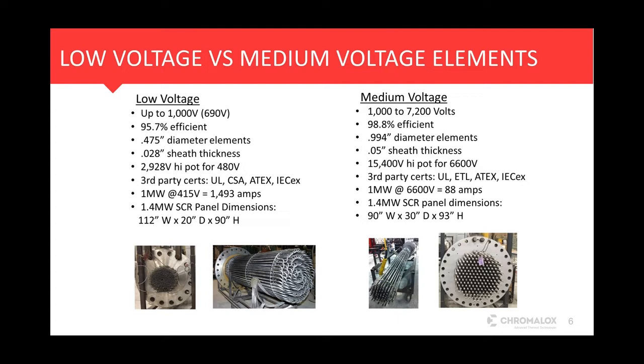So if you look at an example system, 1 megawatt at 415 volts is pulling about 1,500 amps. An equivalent system in the medium voltage realm at 6,600 volts pulls only 88 amps. So that's a drastic downsizing in the infrastructure that's needed to support these systems.